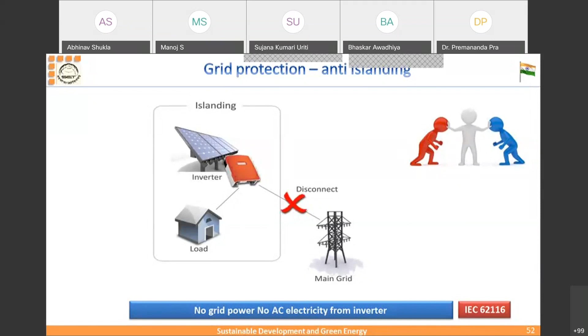So grid protection, let me give you an idea about IEC 62116, in which there is a clause of anti-islanding. So if there is no reference power from the grid, the entire power plant will shut down. Okay. So for on-grid power plants, if there is no reference from the grid, it will never export electricity towards the grid. There is no conversion from DC to AC in the inverter. Okay.